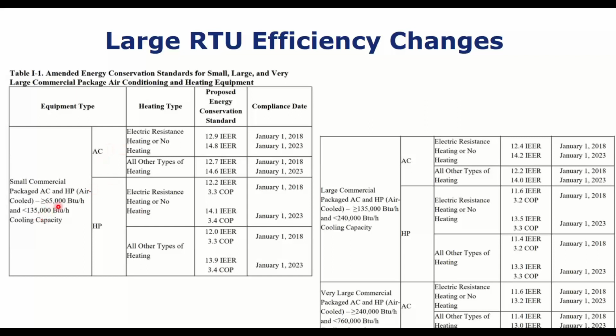So for AC, let's say it's a 10-ton AC unit. This top row is for if I have no heating system or electric heating, since electric heating isn't very airflow restrictive. Then here is all other heating - natural gas, propane, a hydronic coil, something like that. Those are the efficiencies I have to hit today.